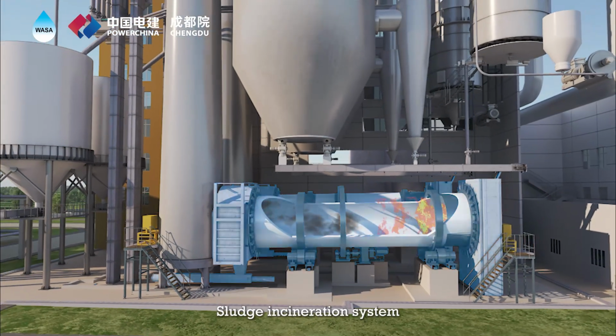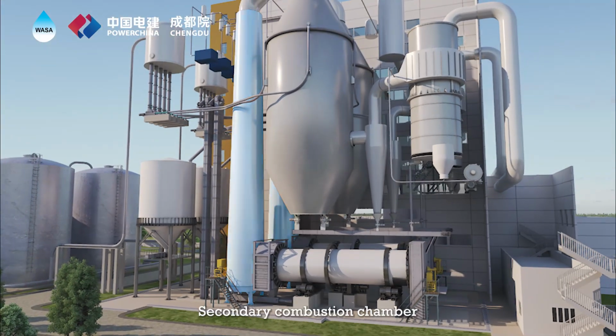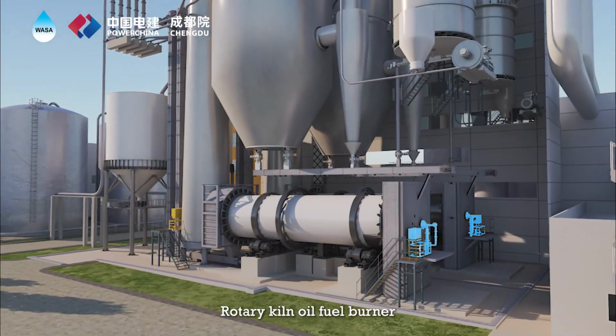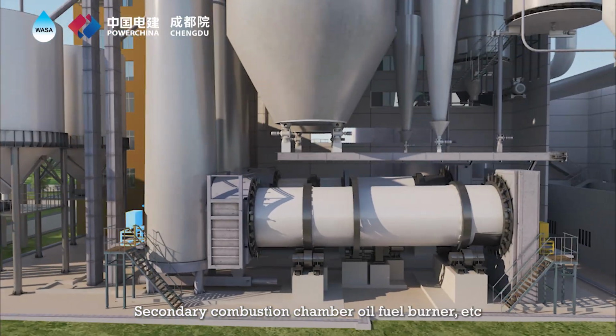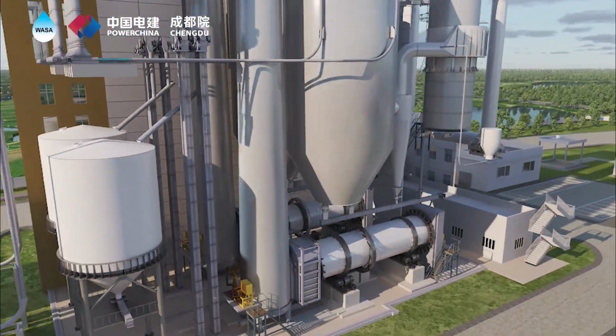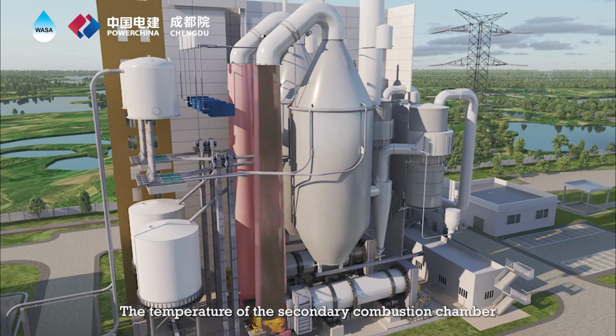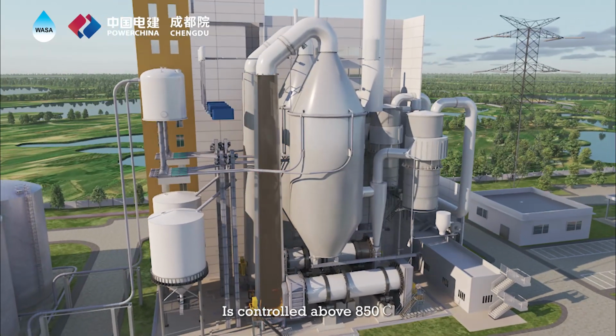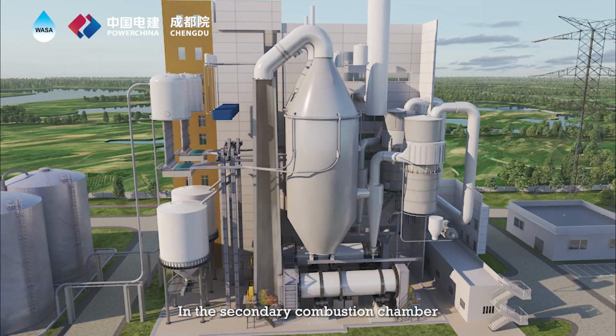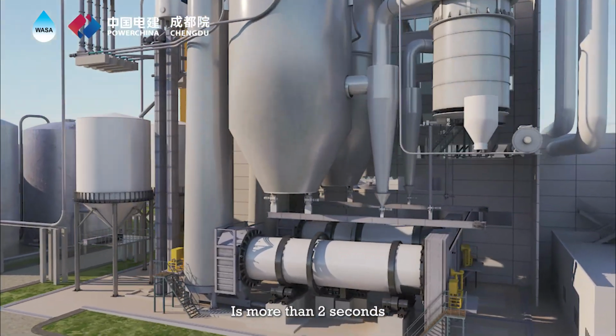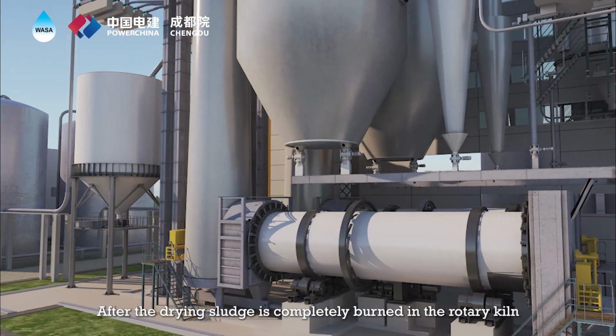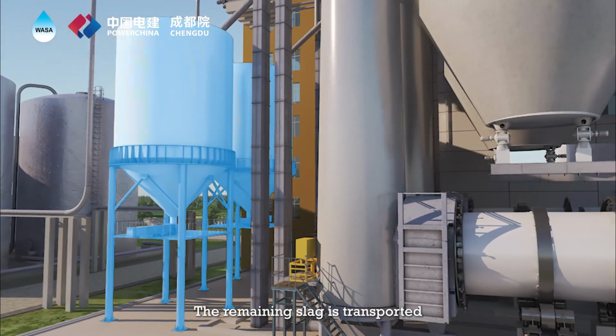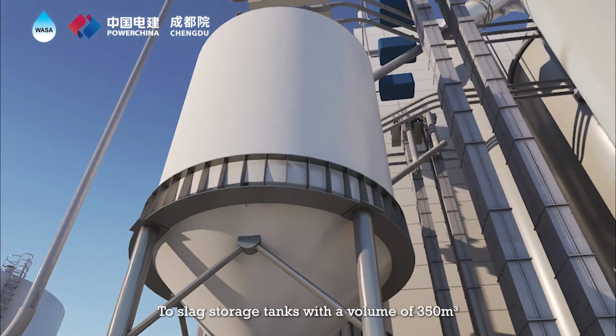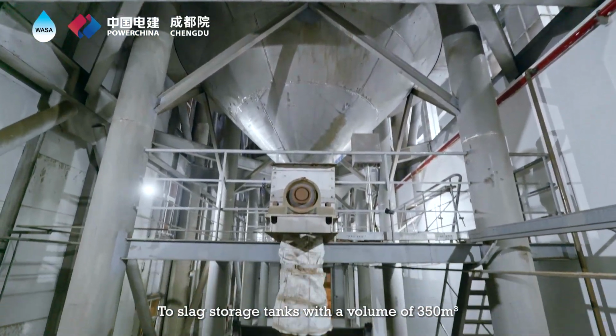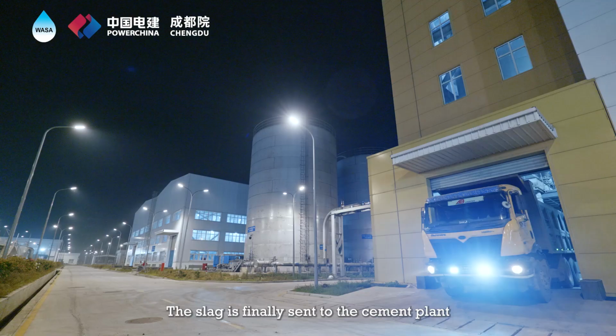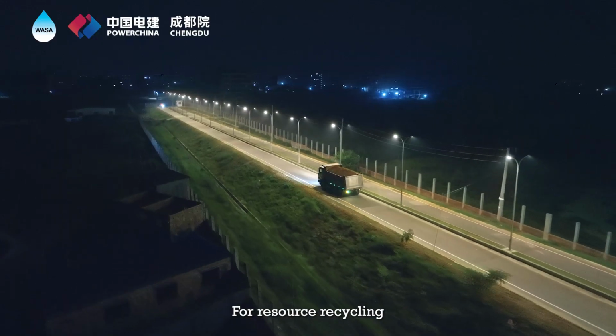system. The sludge incineration system consists of a rotary kiln, secondary combustion chamber, rotary kiln oil fuel burner, secondary combustion chamber oil fuel burner, etc. The temperature of the secondary combustion chamber is controlled above 850 degrees Celsius, and the residence time of the flue gas in the secondary combustion chamber is more than 2 seconds. After the dried sludge is completely burned in the rotary kiln, the remaining slag is transported to slag storage tanks with a volume of 350 cubic meters. The slag is finally sent to the cement plant for resource recycling.